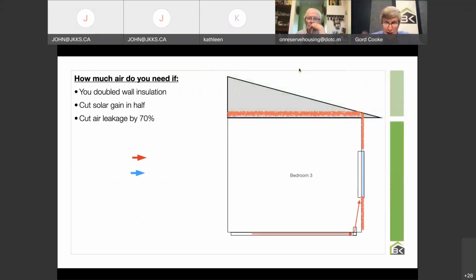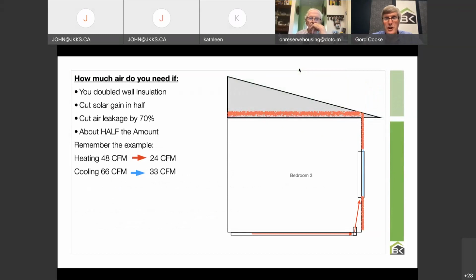And then from there, you would say, I wonder how much... I'm showing both heating and cooling. Not all your buildings, your schools might be cooled, I'm not sure, but probably most of your houses aren't. In many of your climate zones, you don't need much cooling. But to determine how much heat I need for a specific room, I do a whole building heat loss, that is the walls, the floors, the ceilings, but I can do the same calculation for an individual room. You'll see here, this room has one exposed ceiling. I would take its surface area, I would take the wall and its surface area, and I would figure out the BTU loss in that room.